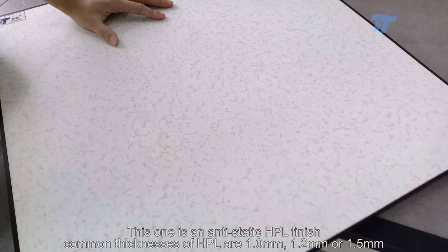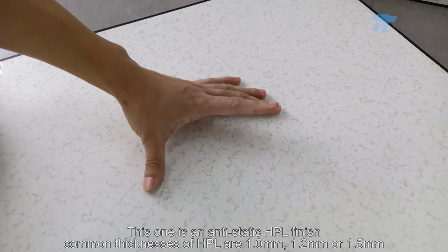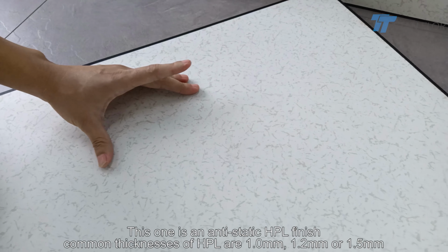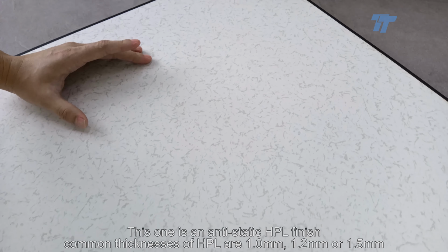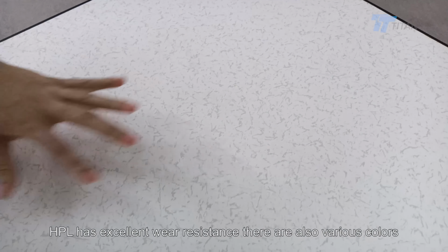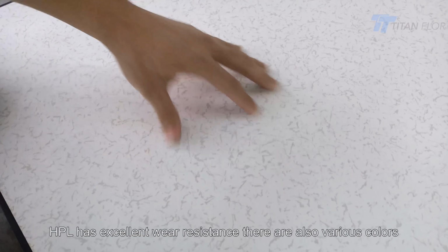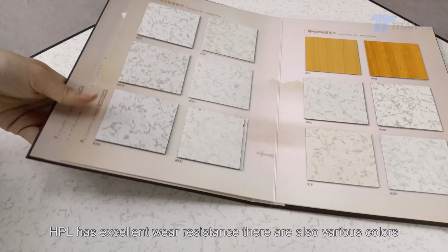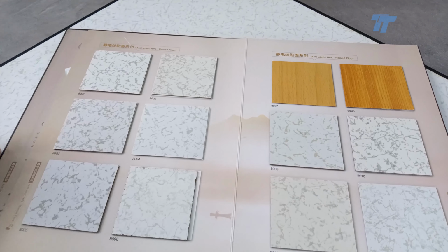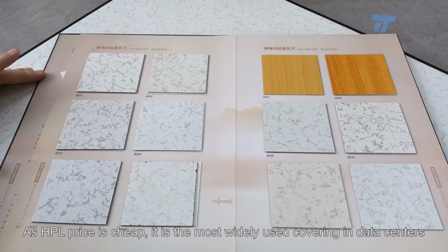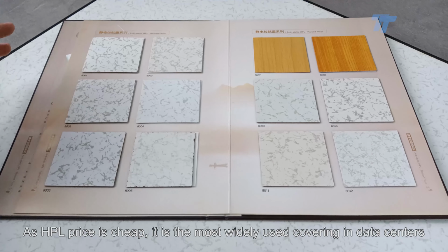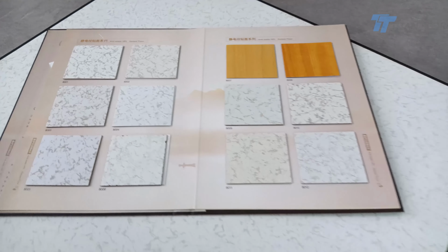This one is an anti-static HPL finish. Common thicknesses of HPL are 1.0mm, 1.2mm or 1.5mm. HPL has excellent wear resistance. There are also various colors. As HPL price is cheap, it is the most widely used covering in data centers.